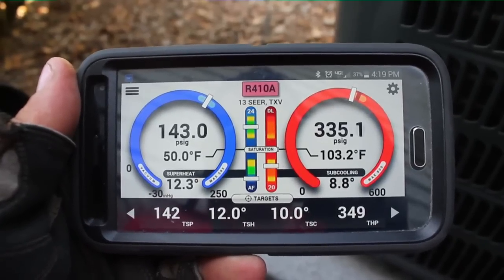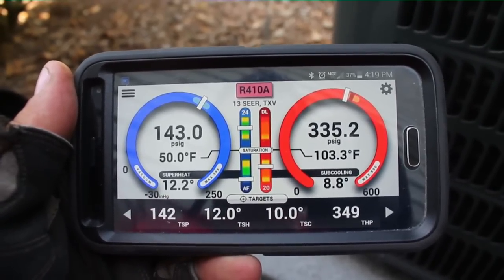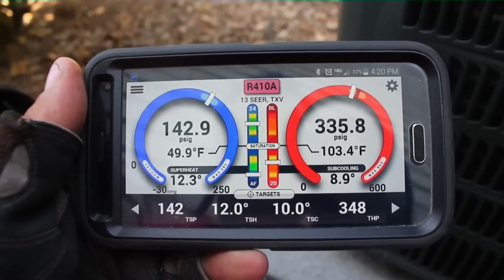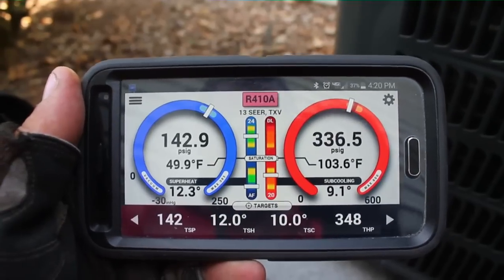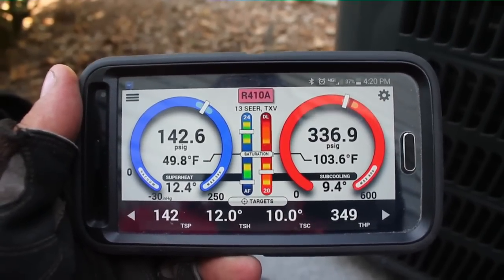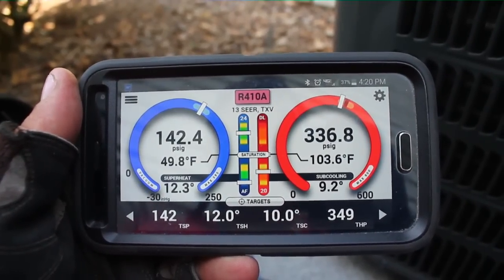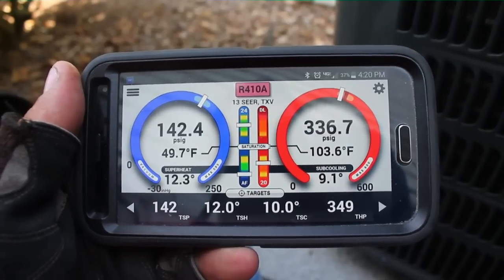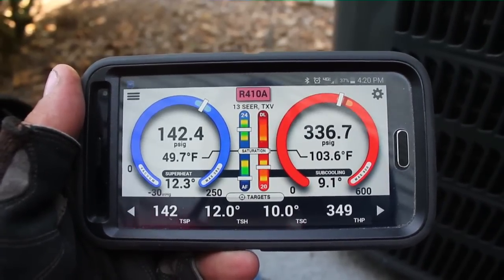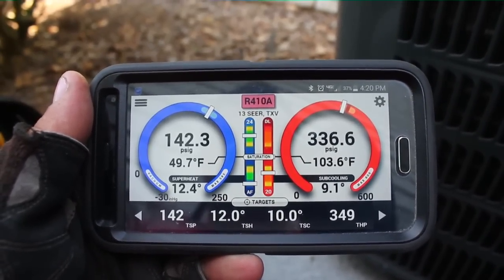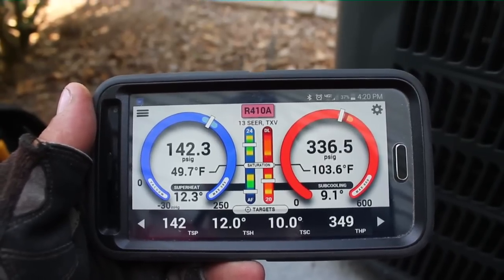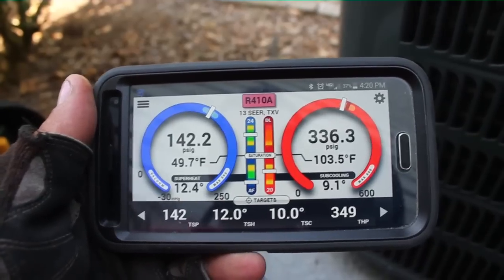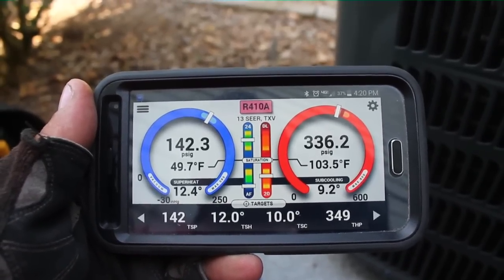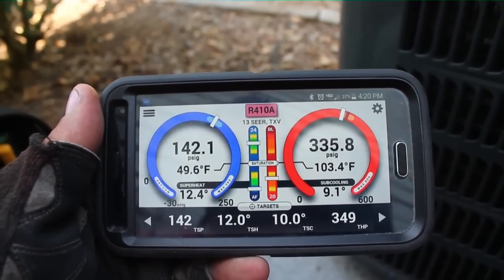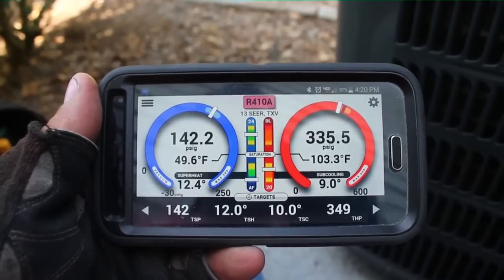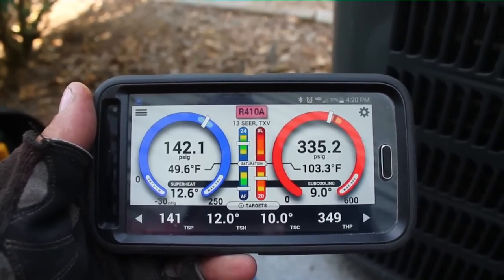We have a 335 over 143 running pressure, 12 degrees of superheat, 8 degrees or almost 9 degrees of subcooling. About right on target for where we need to be. Our head pressure is a little shy of where we need to be, but we are pretty close, and I think we're doing pretty well actually. So we can't really check the system performance right now because it has to be within a certain temperature parameter as far as return air, and we are too hot still. I will wait a little while and maybe we'll get down there before we're done testing. I hope we do. If we do, I will show you guys. Otherwise, I will see you guys on the next one.